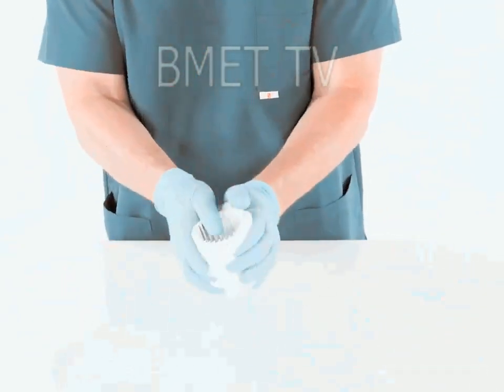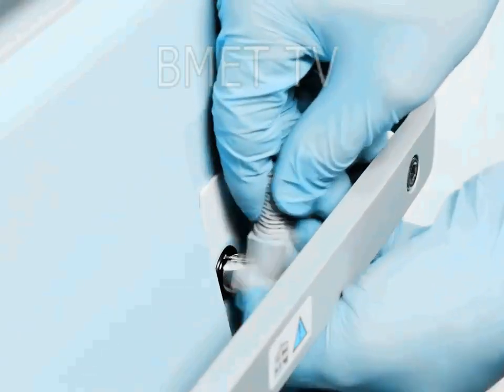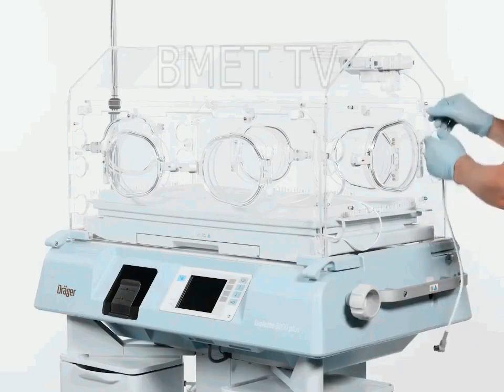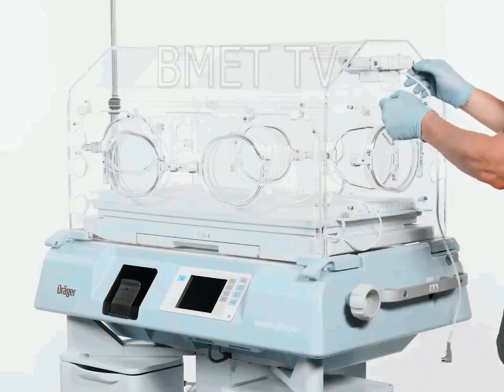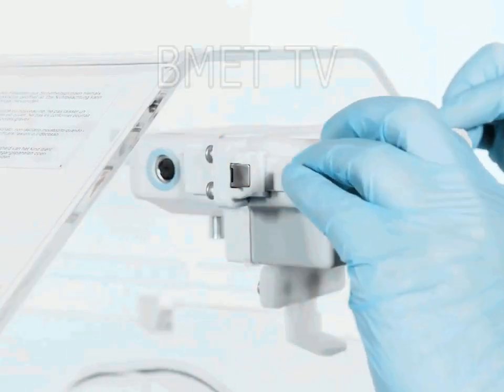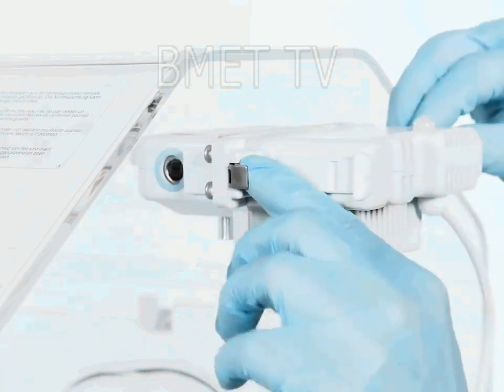The fourth component is temperature control. Simple incubators are controlled by a thermostat which consists of a sensor and a pressure can. The sensor is a thin capillary tube which leads into the pressure can, or expansion chamber. This chamber has a movable metal lid or diaphragm. This closed system contains a liquid or gas which expands when getting warmer. The lid moves and activates a connected electrical switch.